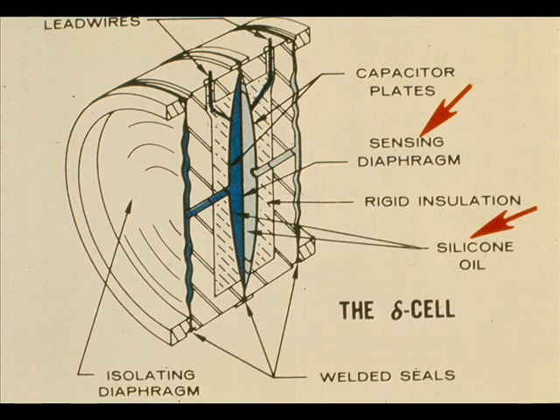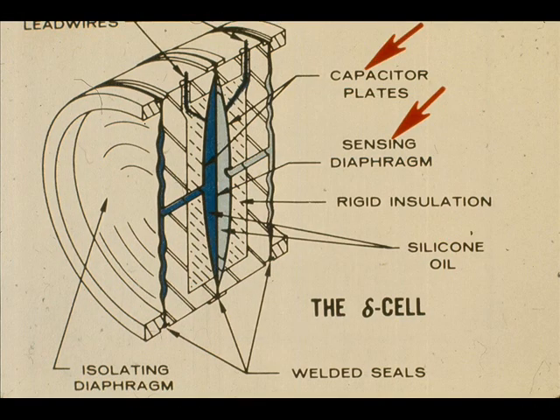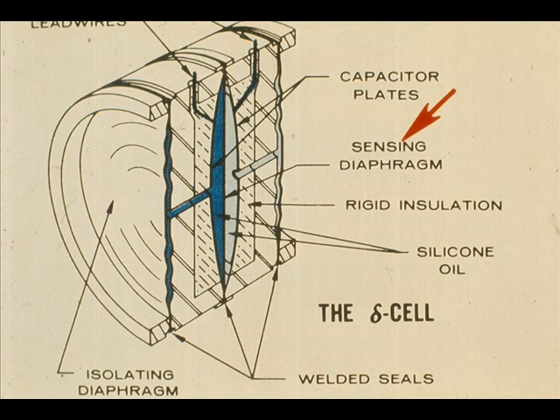A change in differential pressure across the isolating diaphragms is transmitted through the silicone oil to the sensing diaphragm. This changes the position of the sensing diaphragm in relation to the capacitor plates, which in turn changes the capacitance between the sensor and the plates. The movement of the sensing diaphragm and the resulting differential capacitance is proportional to the differential pressure.